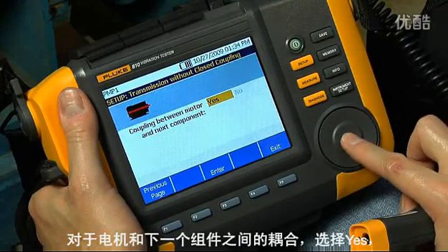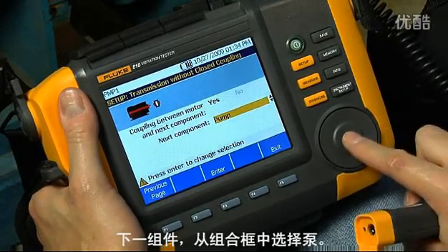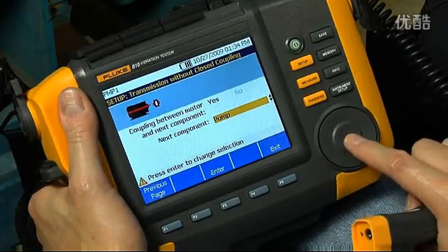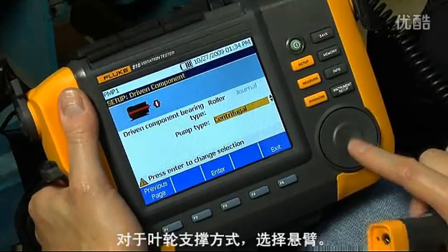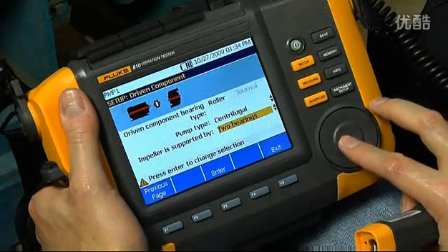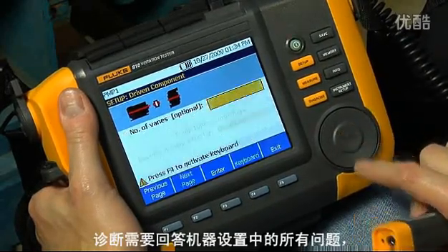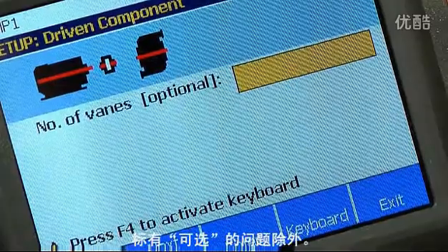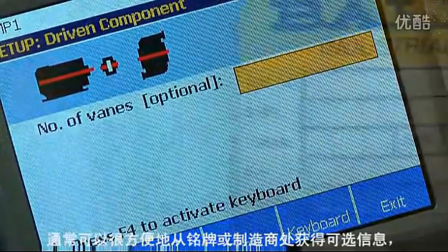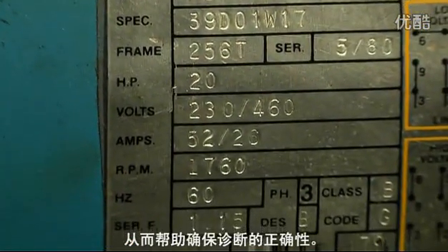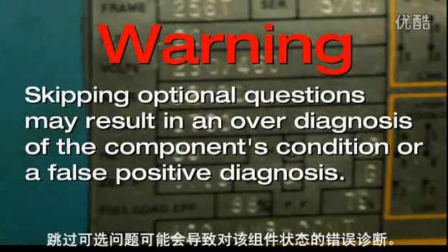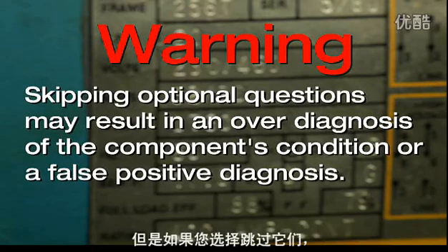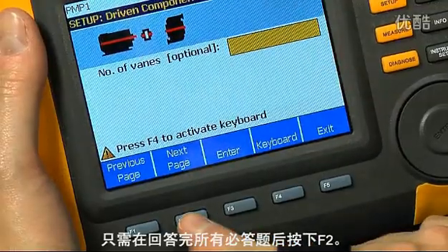Select no for motor close-coupled, and yes for coupling between motor and next component. Select pump from the combo box as the next component. Select roller for driven component bearing type, centrifugal for pump type, and for impeller as supported by, select two bearings. All questions within the machine setup are required to generate a diagnosis except those labeled optional. Optional information helps ensure a correct diagnosis — skipping optional questions may result in an over-diagnosis or a false positive. If you choose to skip them, simply push F2 after answering all required questions.